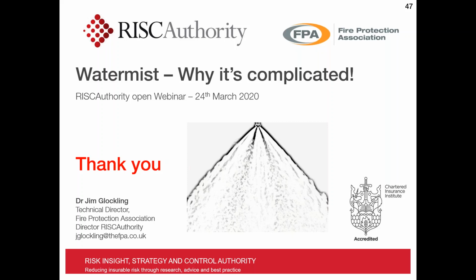Another question: sprinkler systems prevent fire spread until the fire brigade arrive. Is the expectation of the mist system to do the same, or is it designed to extinguish? Well, that goes back to what the core requirements of the system are. Whilst it's well understood within the sprinkler fraternity what a sprinkler system must do, it is clearly a suppression system. A water mist system needs to form part of the overall fire management plan. If it is in a domestic and residential environment, then typically it is to afford people time for egress and evacuation, and not to extinguish. And the water supplies will need to be selected accordingly. Even in other environments where it's expected to extinguish, that's a very specific design criterion, and you will need to consider what happens if that can't happen.